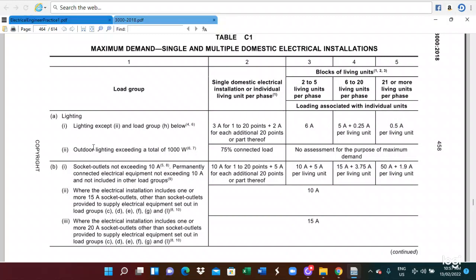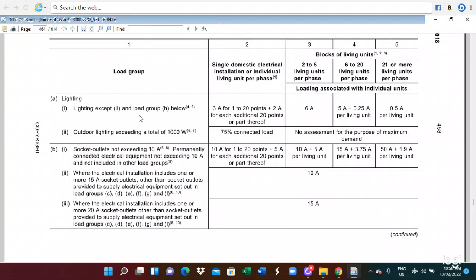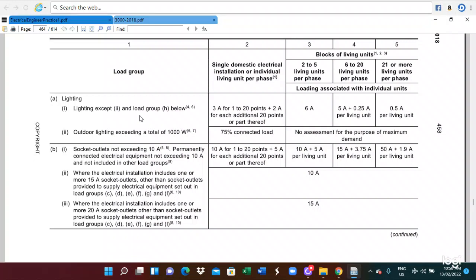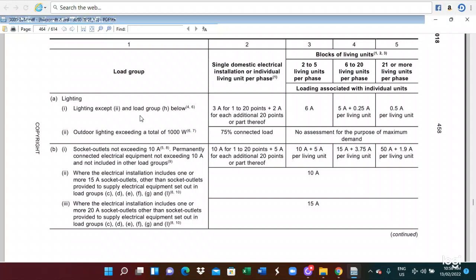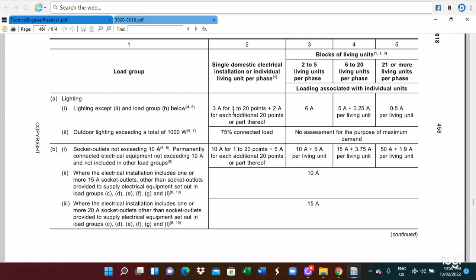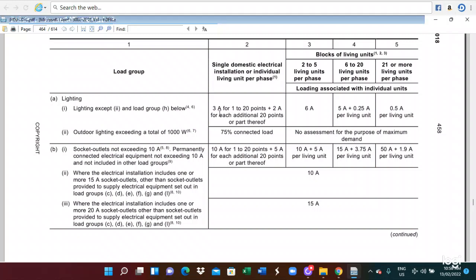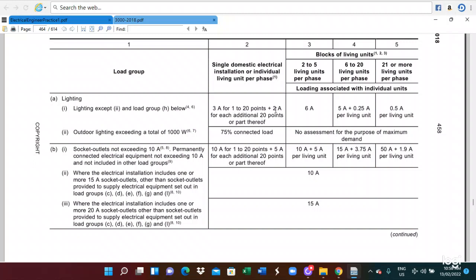And for outdoor lighting, that is 75%. And this is for the lighting point. If you count how many lighting points are in the building, then you can apply the appropriate rule from the building plan. If your installation is a single domestic installation, 1 to 20 is 3 amperes, and for each additional 20 you add 2 amperes. For the block, 2 to 5 living units, you follow this rule, then 6 to 20 and 21 or more. Similarly for socket outlets not exceeding 10 ampere, for single domestic we refer to this rule.